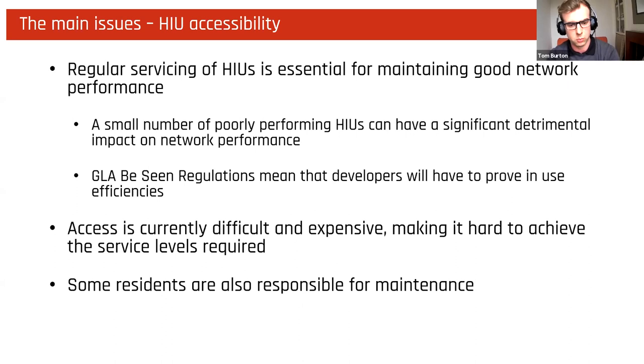With HIUs within dwellings, you need cooperation from residents in order to gain access, and this is a difficult and lengthy process, and as a result quite expensive as well, and this means that 100% service level is really difficult to achieve in practice. What we also see sometimes is that some residents are responsible for maintaining their HIUs, which means you've got third parties maintaining the system who don't know anything about how it has been designed to operate. They don't know the set points of the network, the hot water, space heating. And sometimes the training levels aren't as good as what you would get from a qualified HIU servicing engineer.